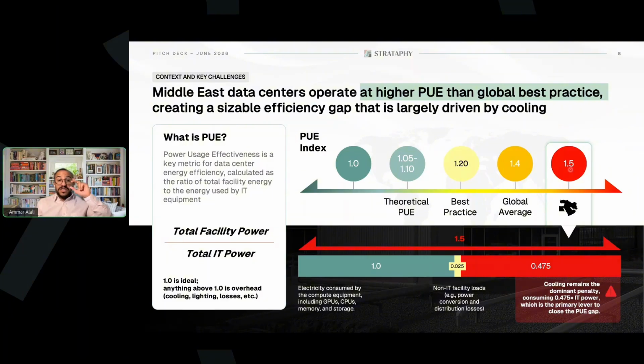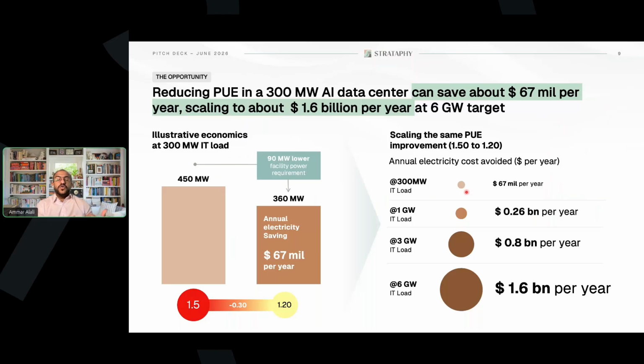Now, for a typical size data center of 300 megawatts, your grid connection needs to meet a potential demand of 450. That's what's called PUE peak. So at peak cooling demand, what does your PUE look like? Even if you only get to that peak demand 1 month of the year, you still need to have infrastructure to meet that maximum peak demand at any given point of the year. So the grid connection needs to be 450.